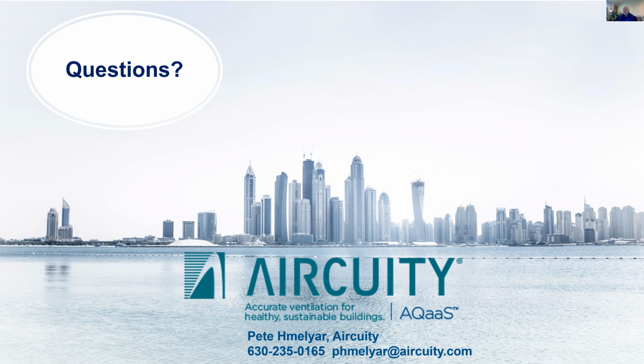Okay, and so following on from that, we've also been asked, can the sensor suite be maintained by site staff, or is it only maintained by Aircuity? Yeah, first off, it's maintained by the local representative for Aircuity, so you have local support. There is some basic training that can be provided. Normally people have the local representative do the sensor swap every 6 months. There's not preventive maintenance, so to speak, because the representative is out there every 6 months to swap the sensors and run the other pump, and there's a small filter in there that's replaced. That's the extent of that.